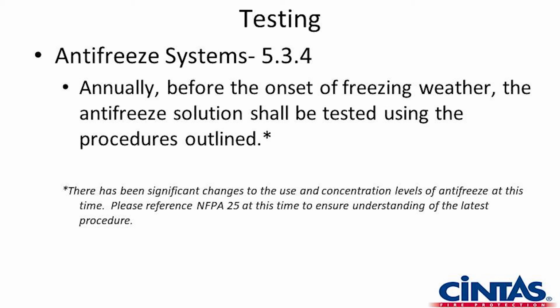In the newer standards, the 2020 standard, it actually speaks to that. Some fire departments are mandating that if the solution is replaced, it's replaced with a UL listed solution. It's causing a lot of problems because it is almost triple the cost of what a non-UL listed solution costs in today's market right now.